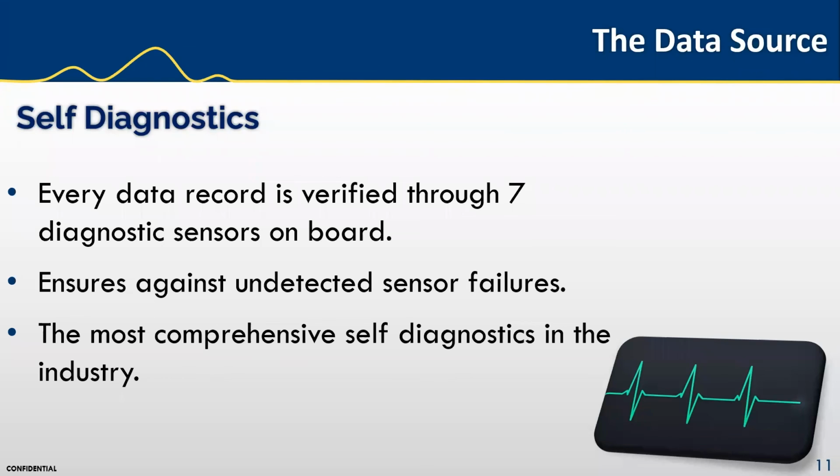So our particle counters have technological advances with every data record verified through 7 sensor diagnostics. So the data is validated as good data from the source. The technology secures the data against sensor failures or if the sample itself is skewed.